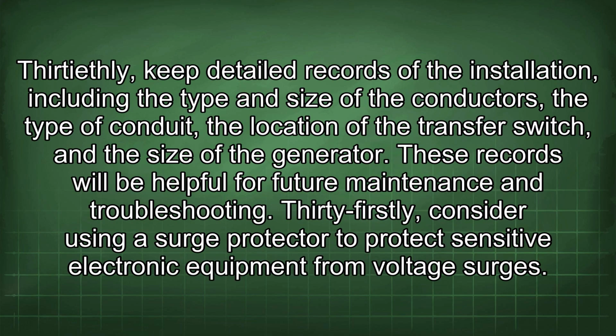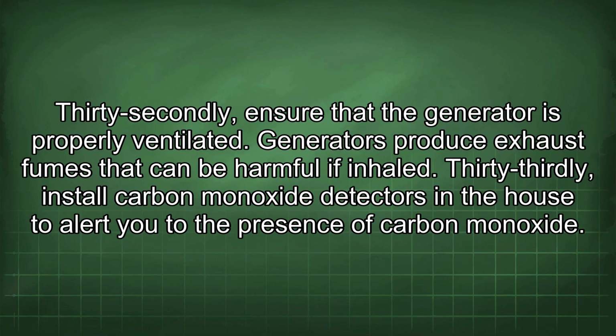30thly, keep detailed records of the installation, including the type and size of the conductors, the type of conduit, the location of the transfer switch, and the size of the generator. These records will be helpful for future maintenance and troubleshooting. 31stly, consider using a surge protector to protect sensitive electronic equipment from voltage surges. 32ndly, ensure that the generator is properly ventilated.